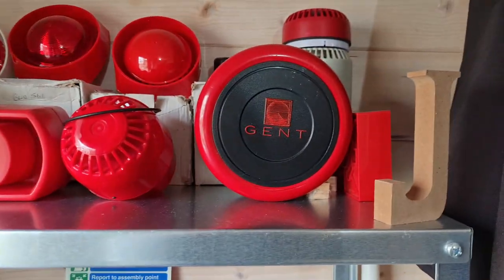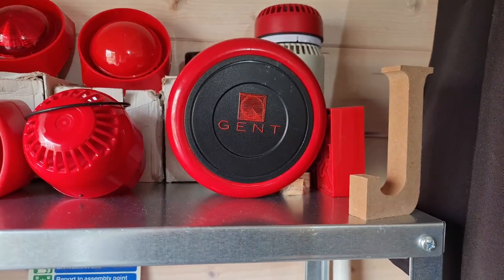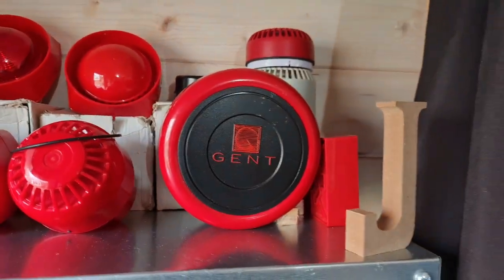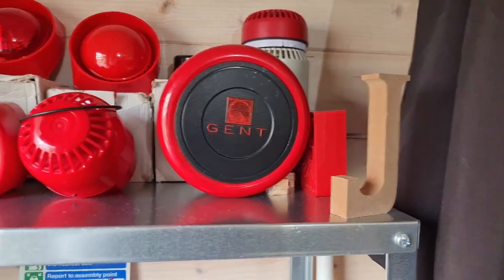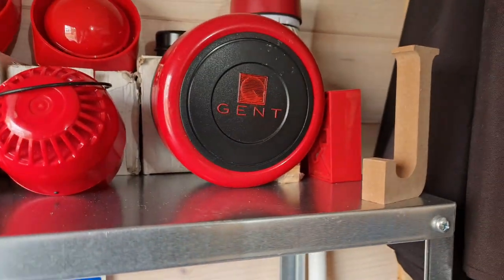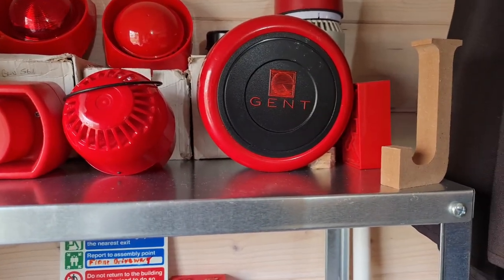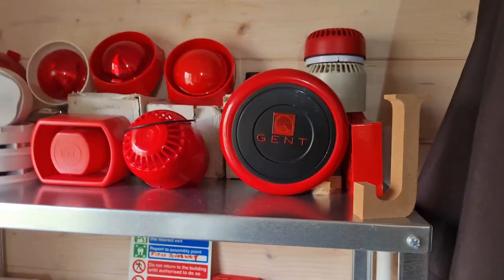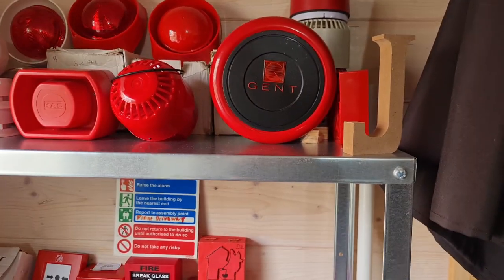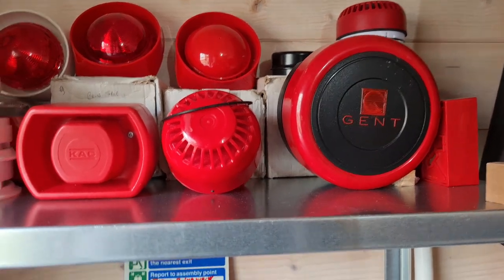It's the only bell I have. Those of you who've been on my channel for a really long time will know I did have a Fulleon centrifugal bell, but I had to get rid of that because it was dead on arrival. I bought it from SD Fire Alarms — they sold it to me without the bolts, then sent those after. When I got the bolt the bell just didn't work properly; the striker would only start sometimes and you'd have to give it a nudge. The motor was just wrong. So I don't like Fulleon bells — I much prefer these Gent ones.